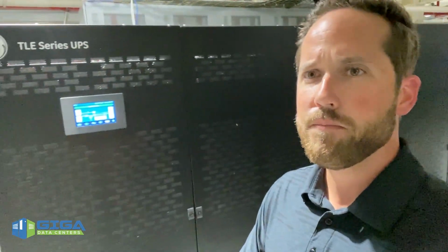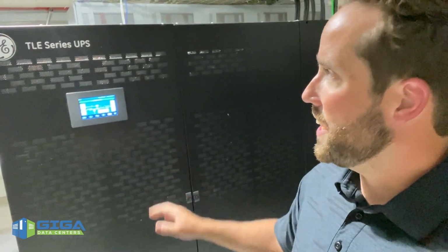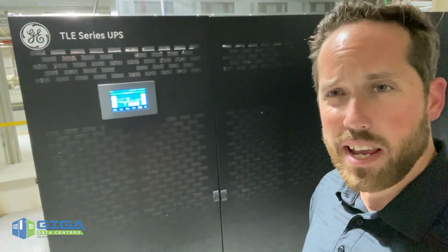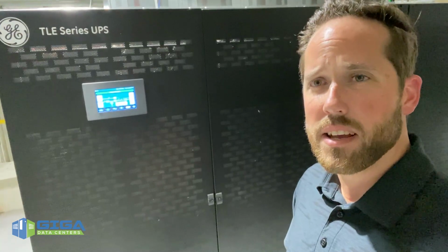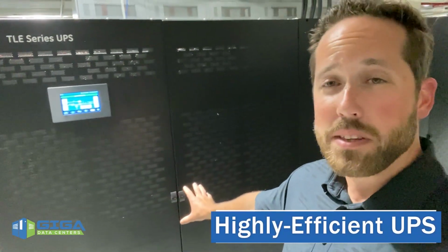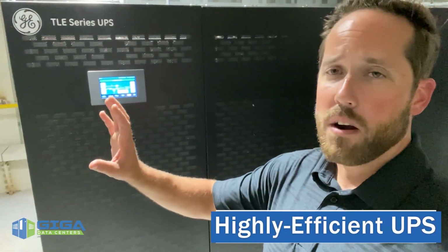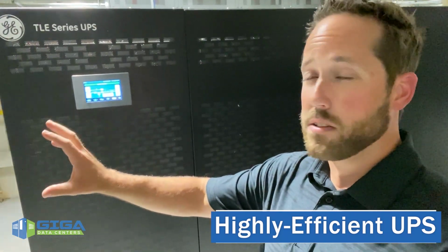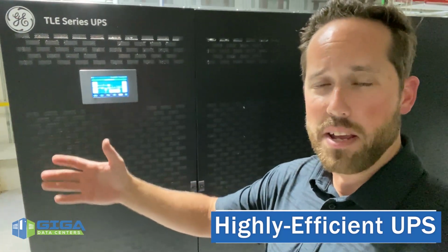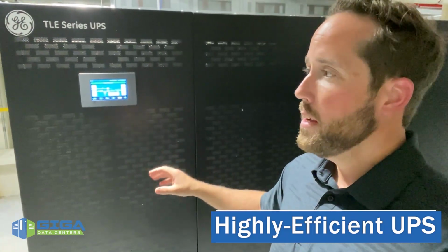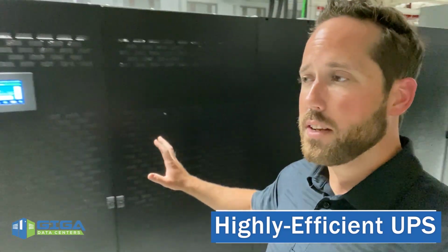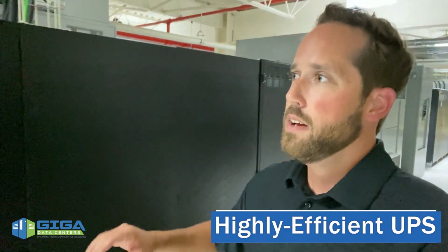Once that power is split into an A and B feed, we utilize the TLE series UPS from GE. These are highly efficient UPSs. Essentially what they're doing is ensuring that the power sent to them from the switches, from Duke Energy, is good, clean power. Assuming that power is good and clean, those UPSs pass it on to our transformers.